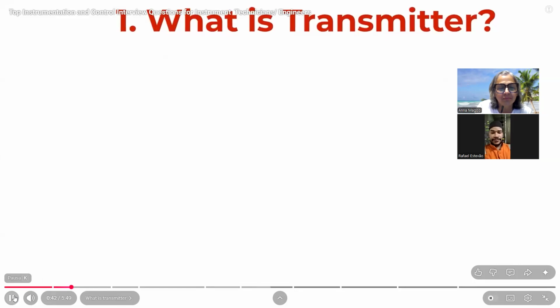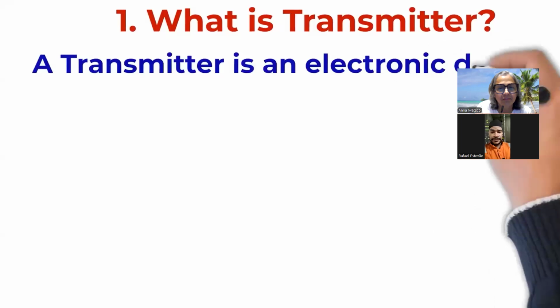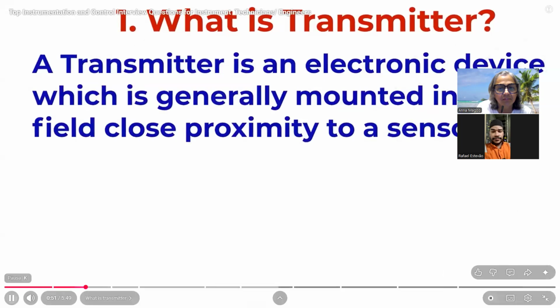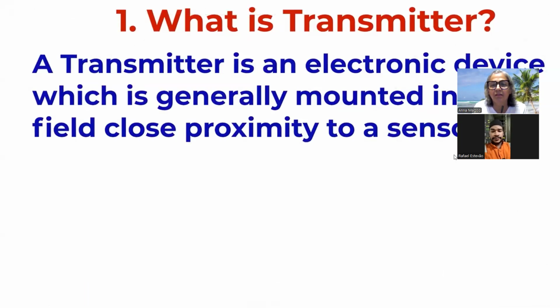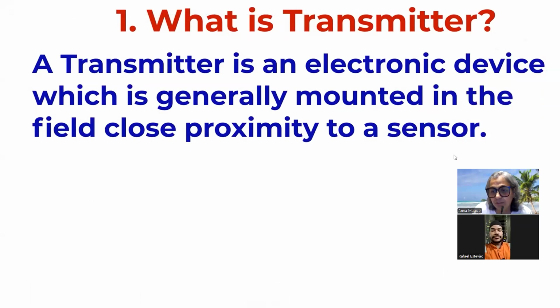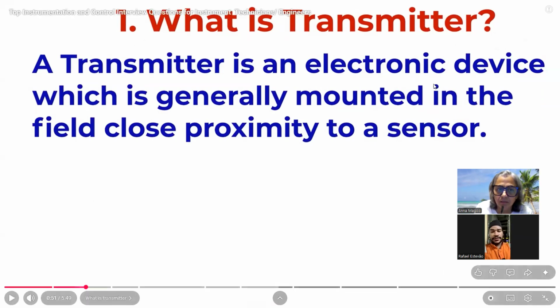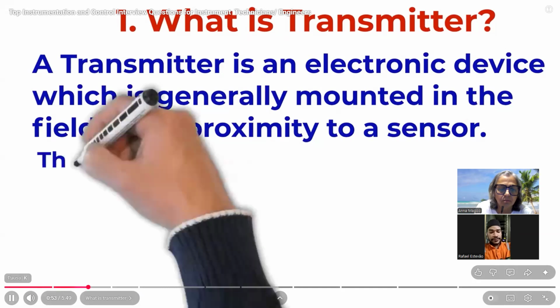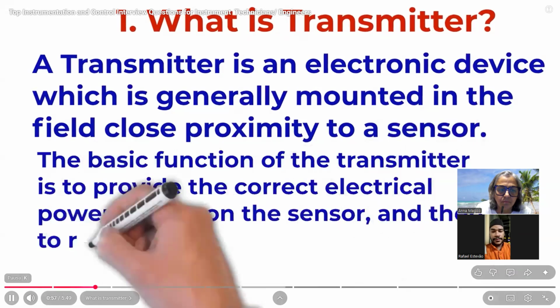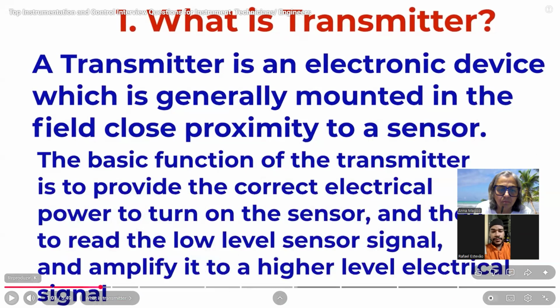Let's see what they say. You need to give a short definition of transmitter. For example, a transmitter is an electronic device which is generally mounted in the field, in close proximity to a sensor. You can read this so you practice the pronunciation. The basic function of the transmitter is to provide the correct electrical power to turn on the sensor, and then to read the low-level sensor signal, and amplify it to a higher level electrical signal, and send that signal a long distance to a controller, or read it.